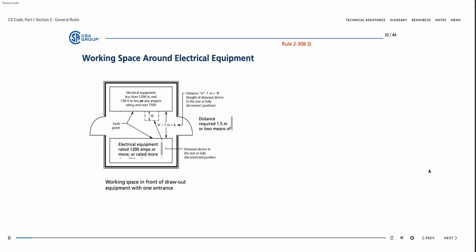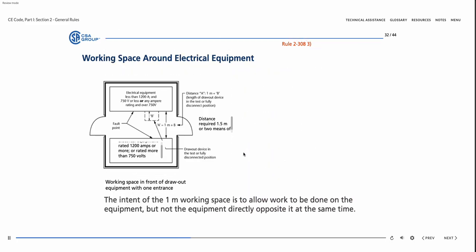The working space of 1 meter around electrical equipment with a rating of less than 1200 amperes and operating on a 750 volt or less system, as shown in the figure, is to be in addition to the space required for the operation of draw-out type equipment in either the connected, test, or fully disconnected position. The intent of the 1 meter working space is to allow work to be done on the equipment, but not the equipment directly opposite it at the same time.